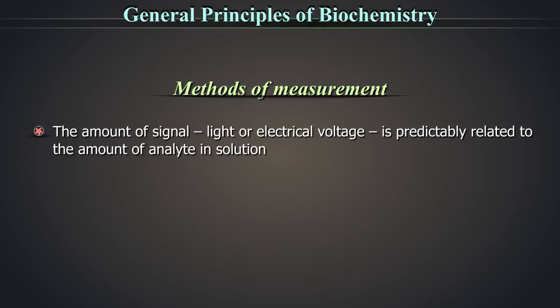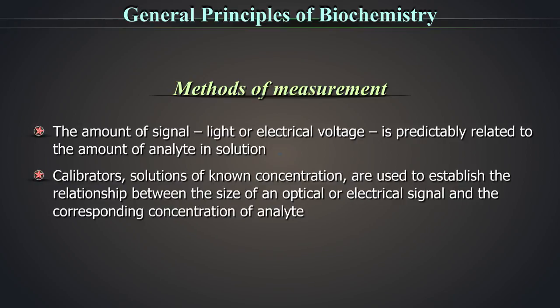The amount of signal, light or electrical voltage, is predictably related to the amount of analyte in solution. Calibrators, solutions of known concentration, are used to establish the relationship between the size of an optical or electrical signal and the corresponding concentration of analyte.